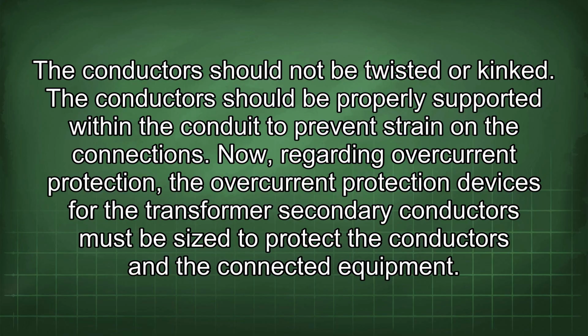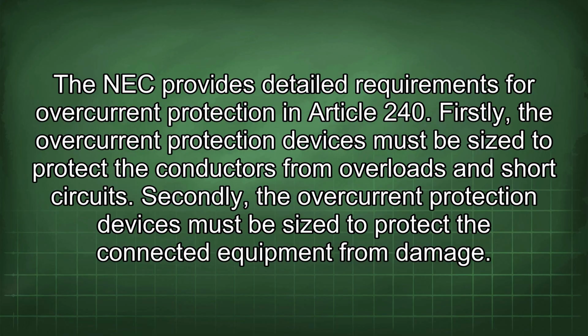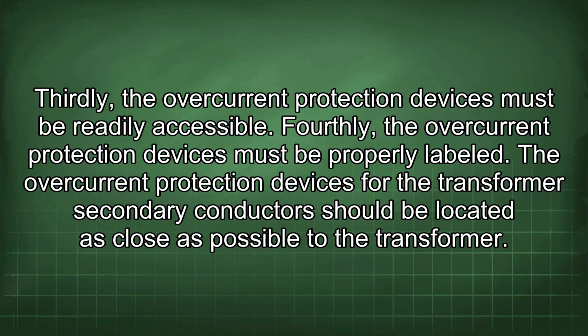Now, regarding overcurrent protection, the overcurrent protection devices for the transformer secondary conductors must be sized to protect the conductors and the connected equipment. The NEC provides detailed requirements for overcurrent protection in Article 240. Firstly, the overcurrent protection devices must be sized to protect the conductors from overloads and short circuits. Secondly, they must be sized to protect the connected equipment from damage. Thirdly, they must be readily accessible. Fourthly, they must be properly labeled.